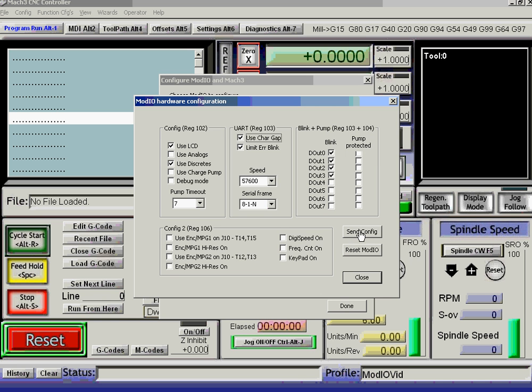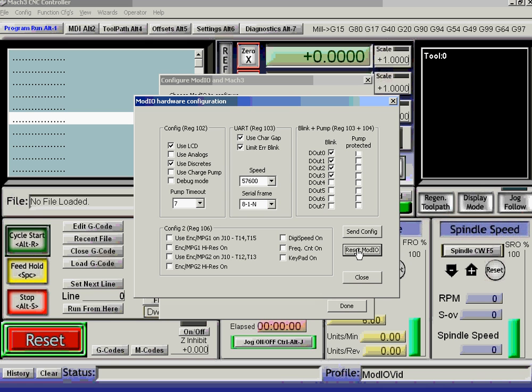So send is going to send it to the ModIO. You get a little bit of flashing on its red and green LEDs. And that configuration won't take effect unless we reset it. So I reset it. Its LCD now displays the configuration. I've got the serial number. I've got the baud rate it's running at. I've got what ID.